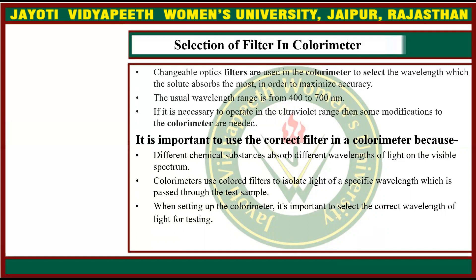The usual wavelength range is from 400 to 700 nm. If it is necessary to operate in the ultraviolet range, then some modifications to the colorimeter are needed. It is important to use the correct filter because different chemical substances absorb different wavelengths of light on the visible spectrum. Colorimeters use colored filters to isolate light of a specific wavelength, which is passed through the test sample, so when setting up the colorimeter it is important to select the correct wavelength of light for testing.